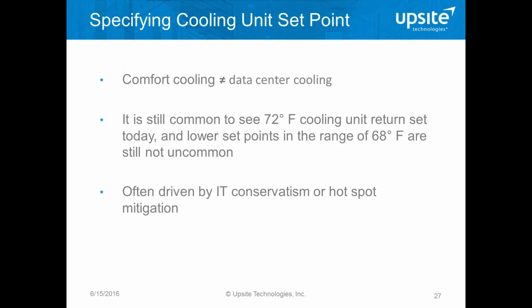So the key thing here is data center cooling is not the same as comfort cooling, despite the common practice in many data centers around the world today. And by that I mean comfort cooling, where we have a thermostat with some set point, and whenever the return air exceeds that set point, we fire up the air conditioning to cool the whole space off, as opposed to the best practice for data center cooling, where we just create a set point that, with good airflow management, should only be maybe 2 or 3 degrees below the maximum IT inlet temperature in the data center. And that allows us then to get access to the increased chiller efficiency and access to more free cooling hours that come with these decisions.